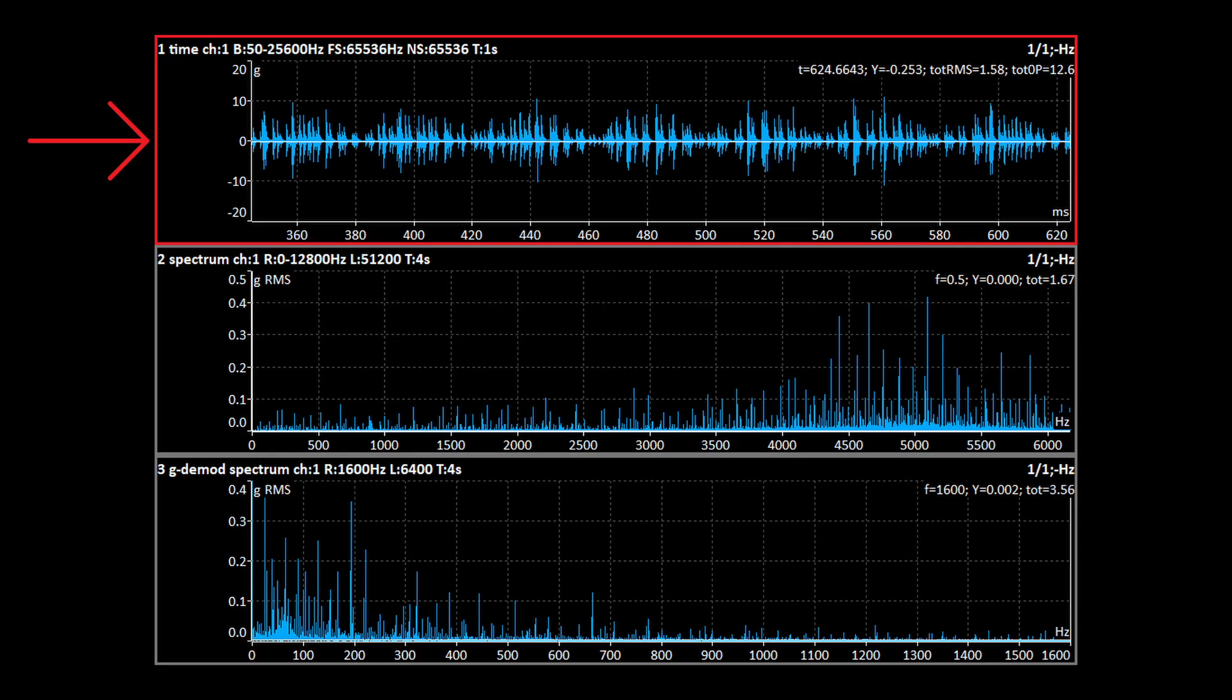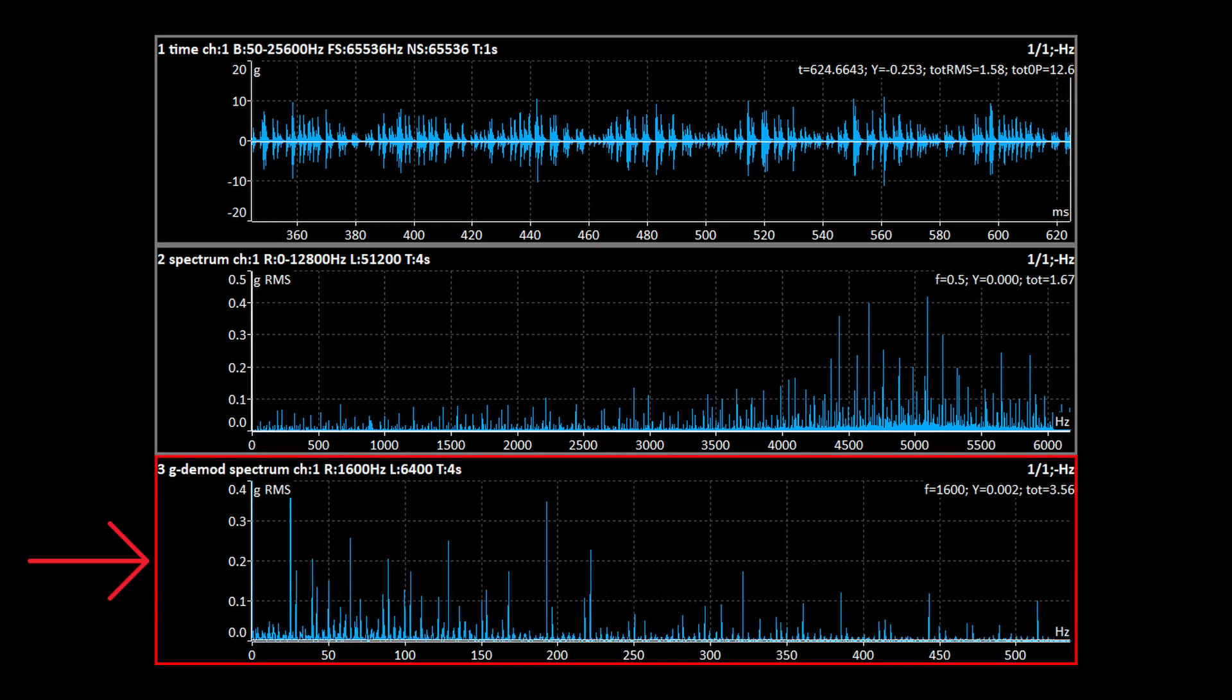We can even see this variability in the time signal. When the sum of the forces is the highest, the shocks are the strongest. When it is the lowest, the shocks are the weakest. Let's zoom into the demodulated spectrum and look for sidebands. Both BPFO and BPFI have sidebands, as do their harmonics.